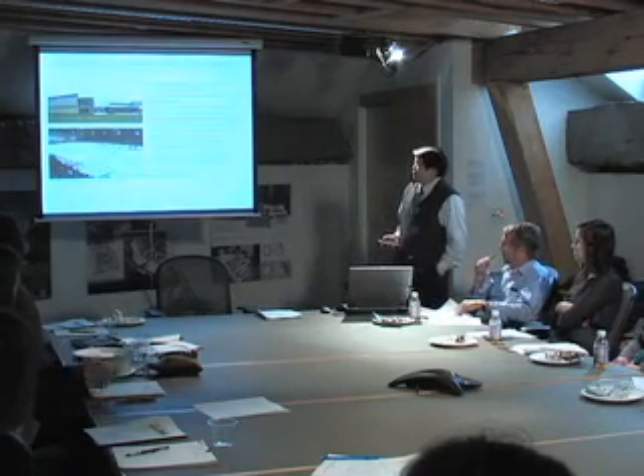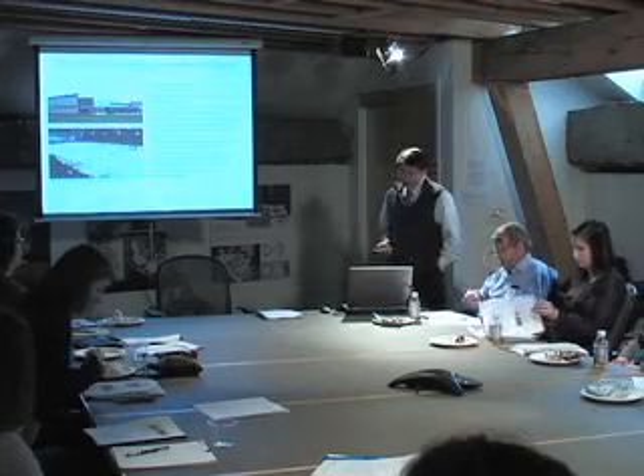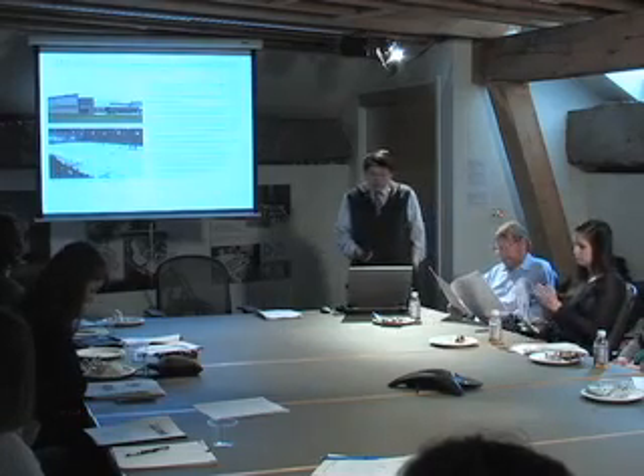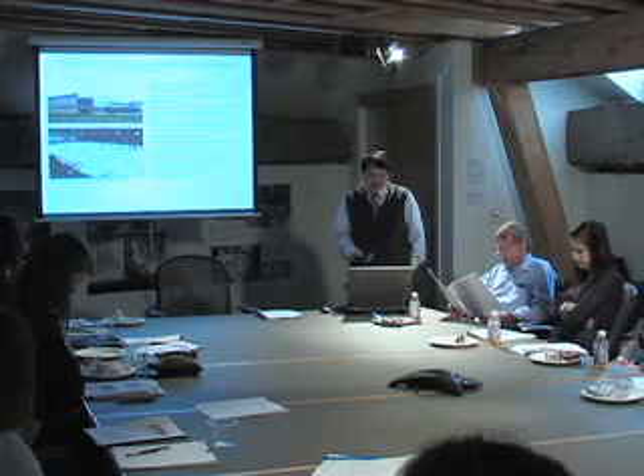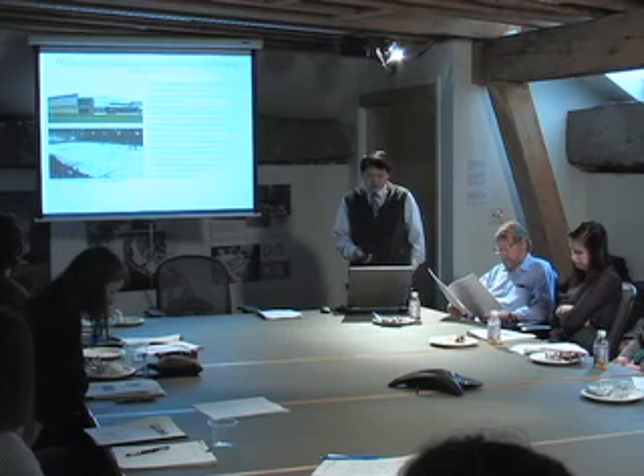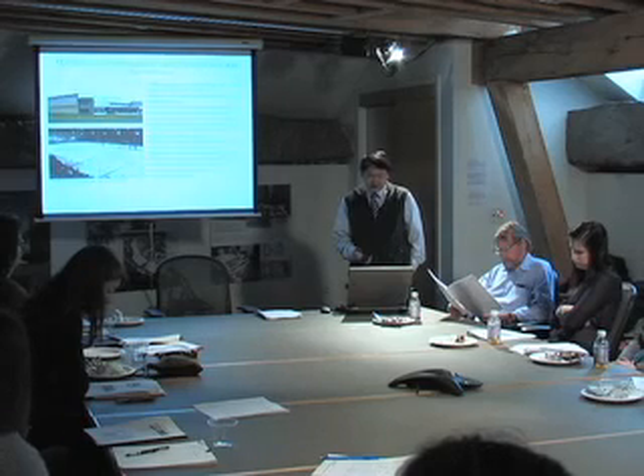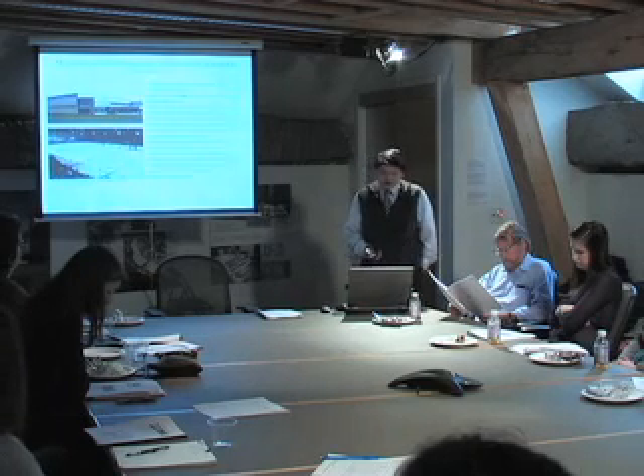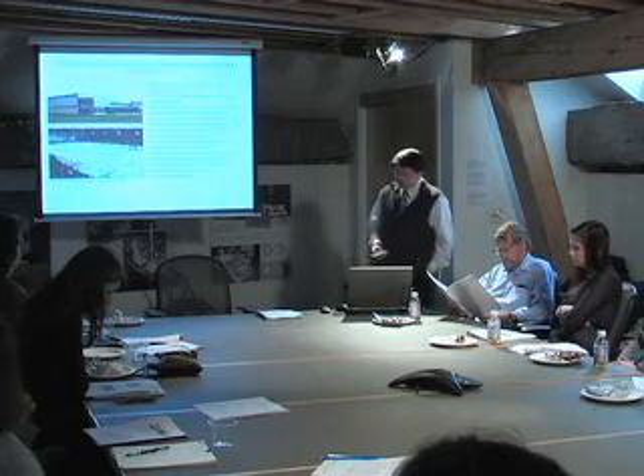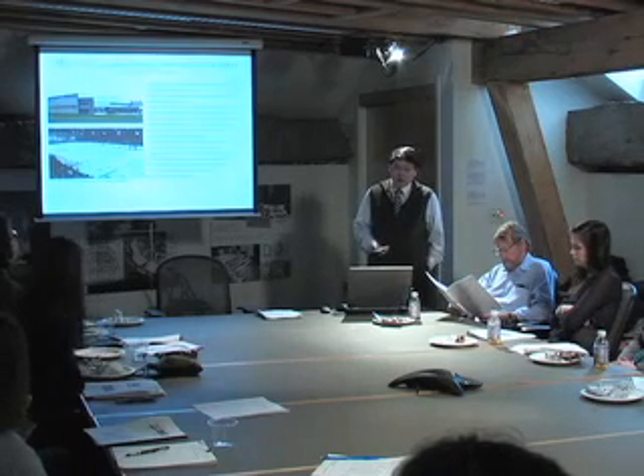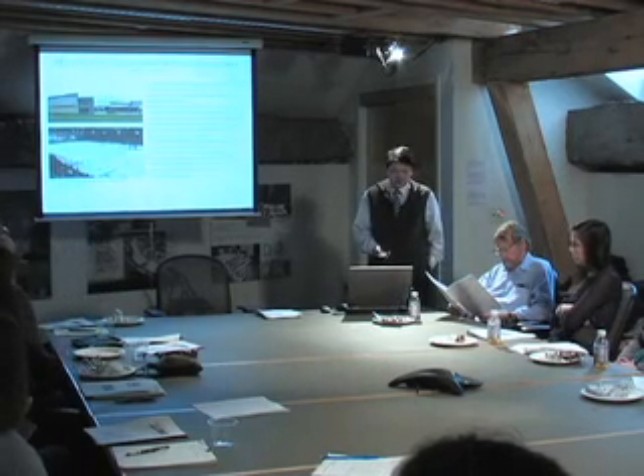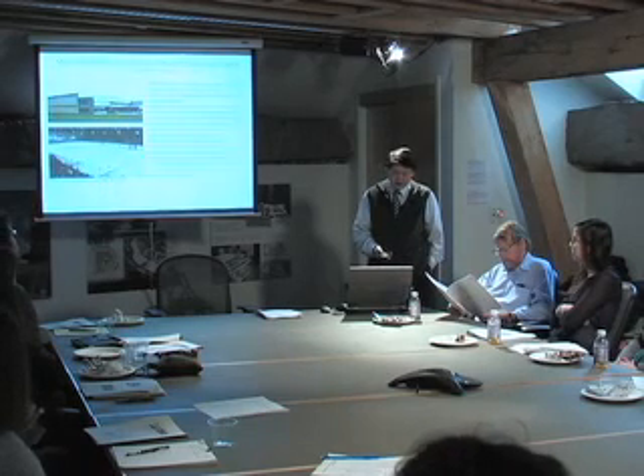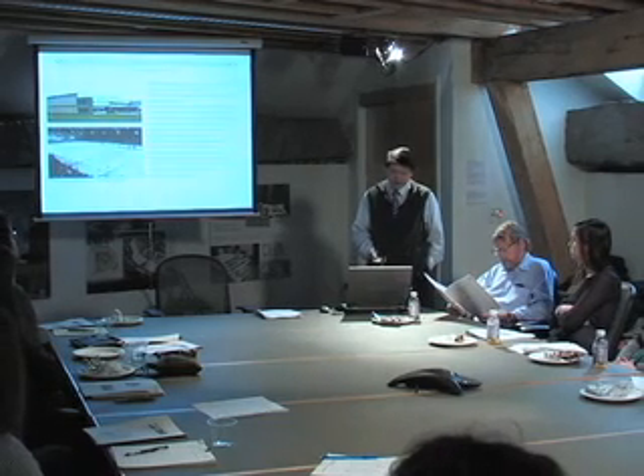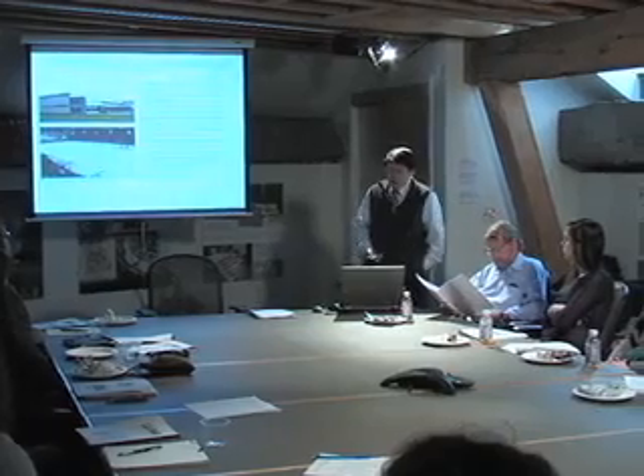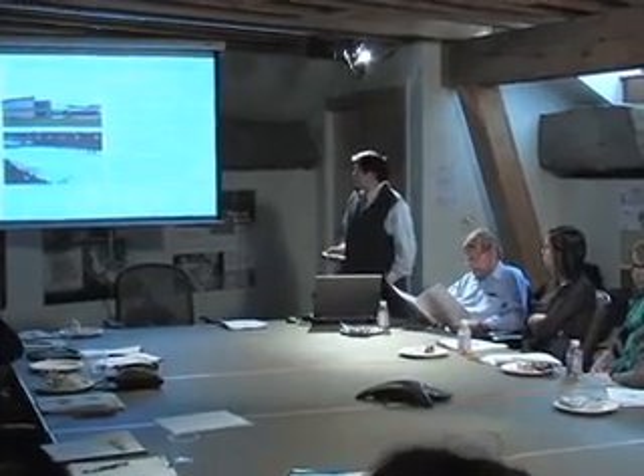Mistry Community Center in North Quebec, Canada. It's a community building, 75,000 square feet, has ice arenas, locker rooms, gym, fitness centers, libraries, fast food, and offices. Now the arena is a very high energy consumption place because you have heating and cooling going on simultaneously. You have to cool the ice arena and also heat the space for comfort. So they built a 28 borehole geothermal system.